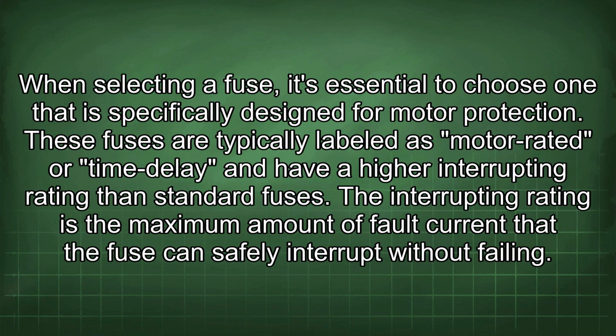When selecting a fuse, it's essential to choose one that is specifically designed for motor protection. These fuses are typically labeled as motor-rated or time delay and have a higher interrupting rating than standard fuses. The interrupting rating is the maximum amount of fault current that the fuse can safely interrupt without failing.